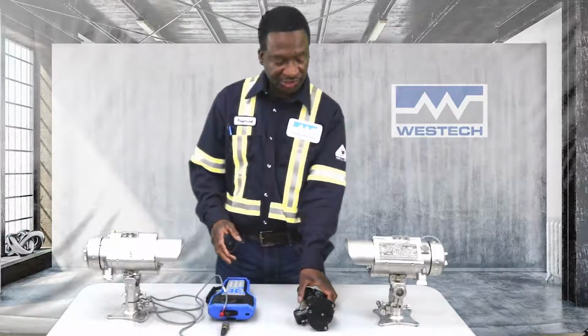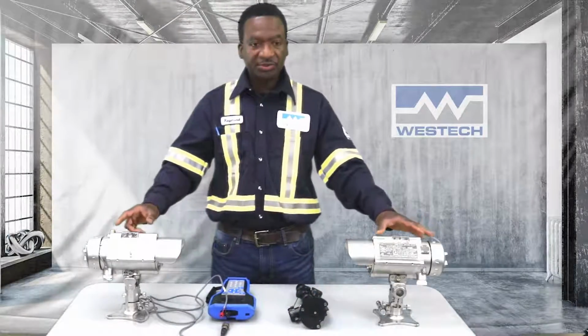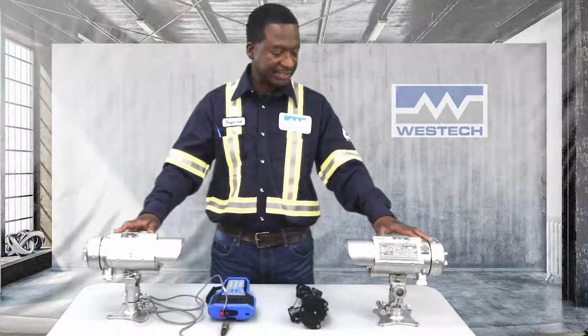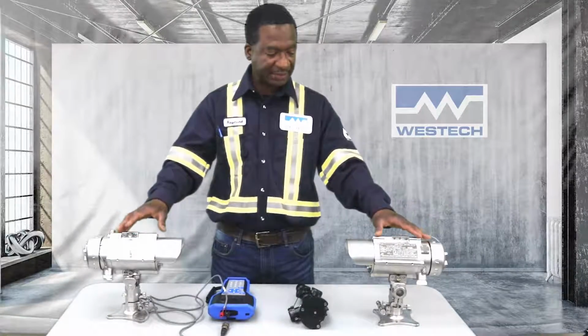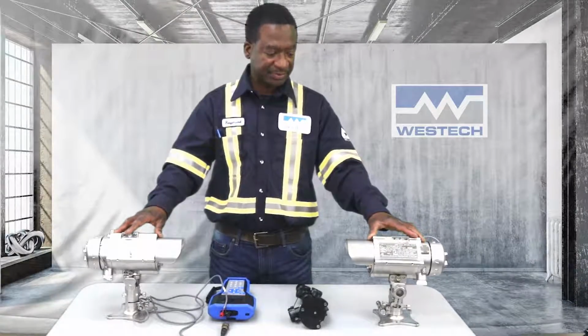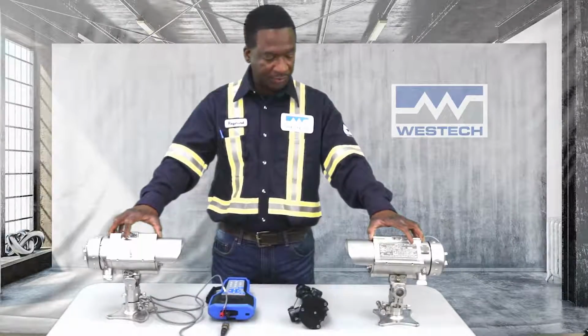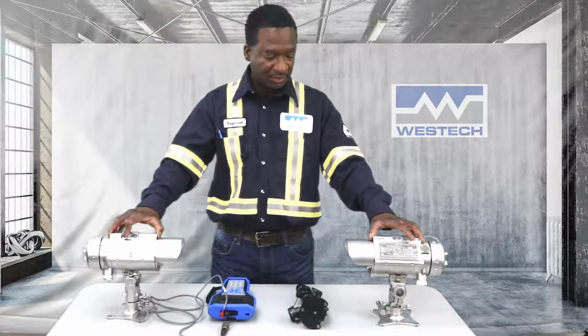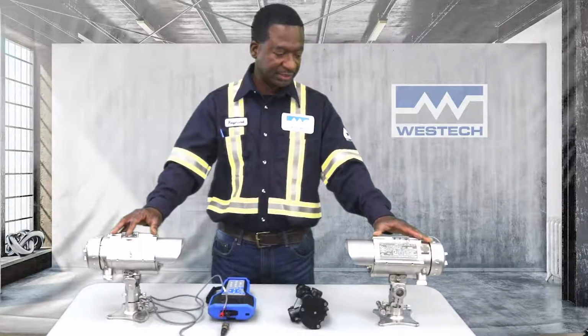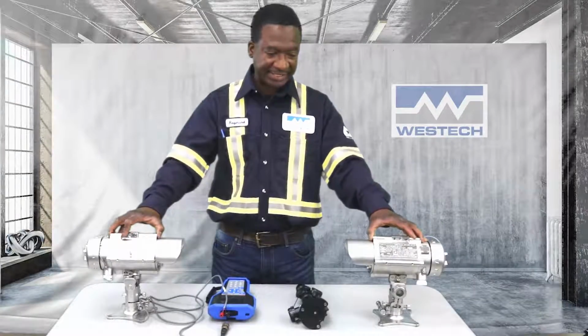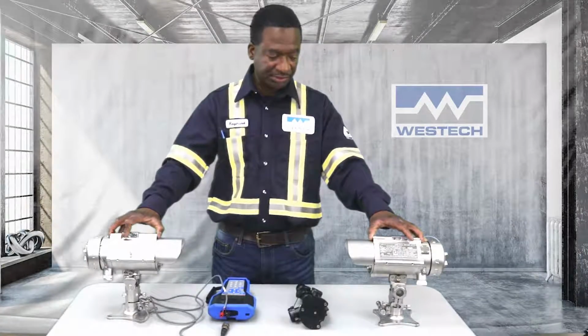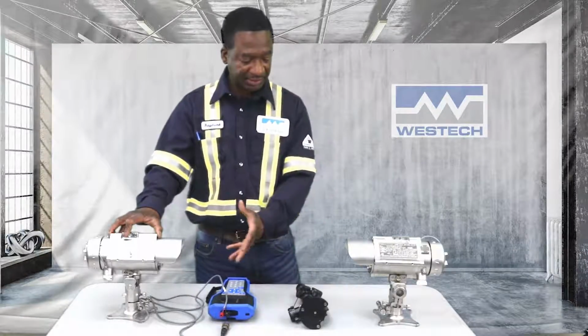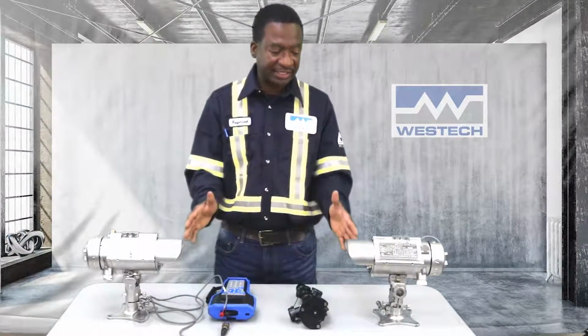Once alignment is achieved, a zero should be done, a zero calibration that is. That is to say, you're accepting the alignment as being the reference point for the detection system. Once you're about to do this, ensure that there are no gases or obstructions in the line of sight of the detector. In other words, the path is clear.